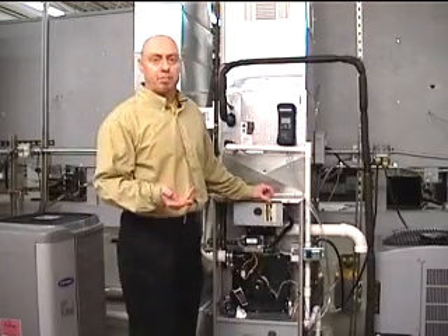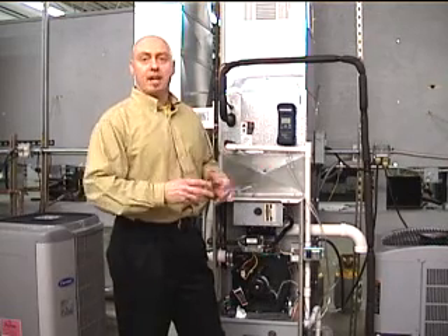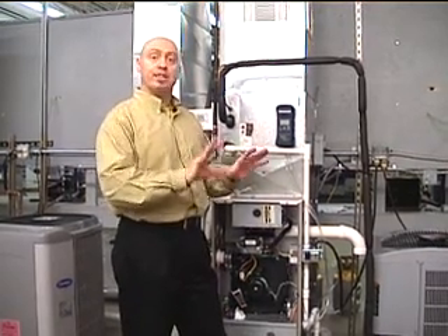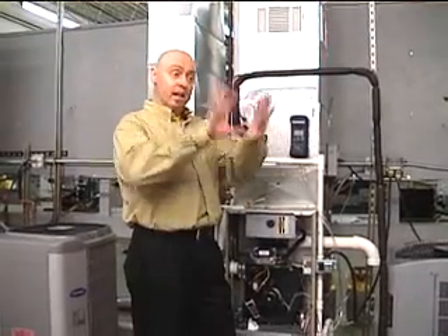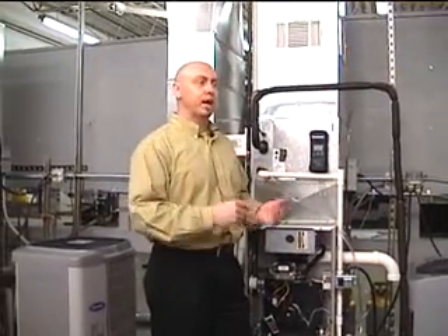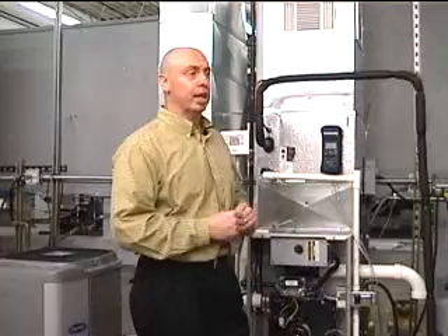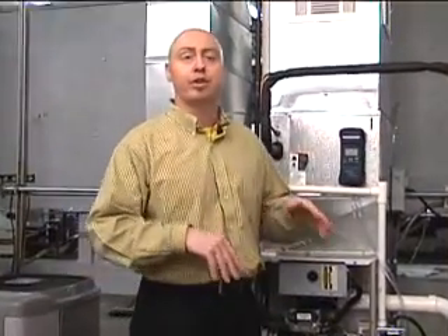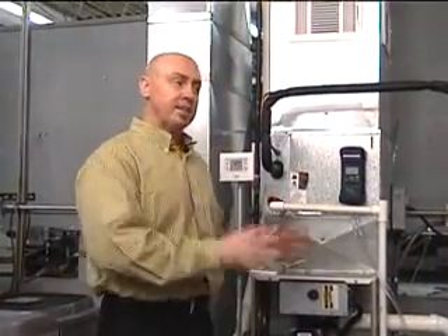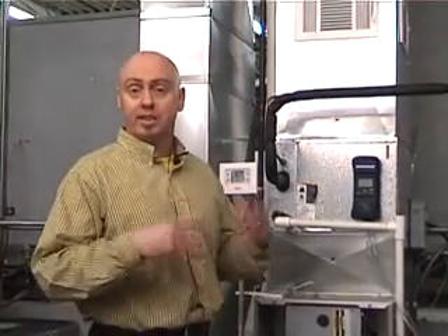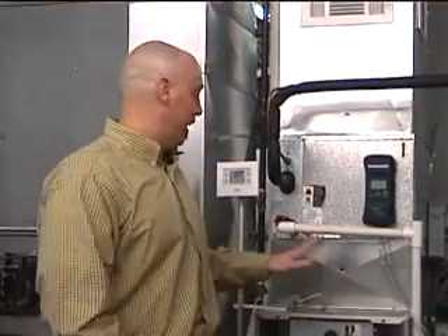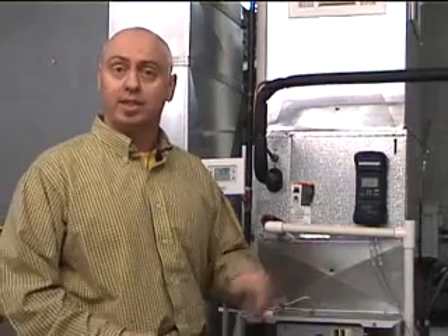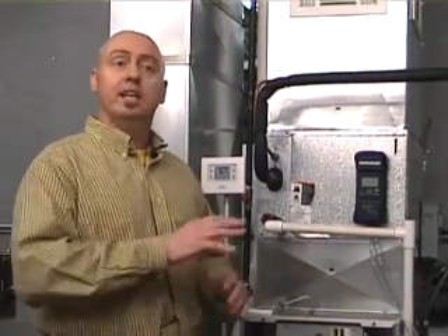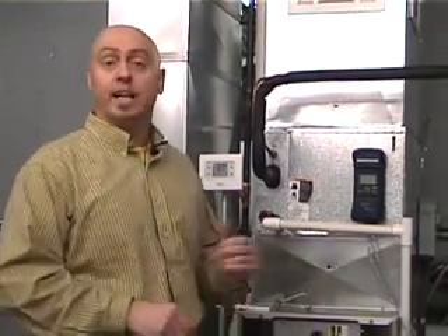Now, when you're checking static pressure, what we're talking about is the pressure that's exerted on all the walls of the duct all the way around equally. There's different types of pressure. We're not going to go into all the pressures because there is velocity pressure, total pressure, things like that. But specifically today, I want to talk about static pressure, or the resistance that's in that duct system. And one way you can do that is by making two holes into the system. What we want to do is evaluate the entire system, the supply side and the return side, all at one time. So you have to punch two holes into the system in order to get those numbers.